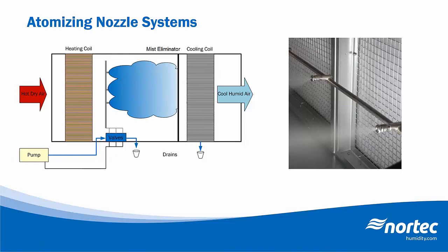Now, as I mentioned, unlike evaporative media systems, as soon as there's a demand for the system to start, the system will start spraying water immediately. So one of the nice things about these systems is they're capable of stage control, so they're able to control to a plus or minus 2% control accuracy, unlike an evaporative media system.